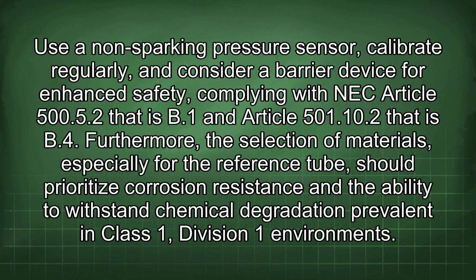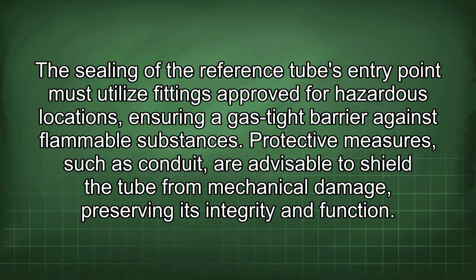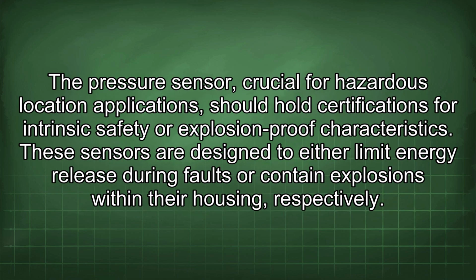Furthermore, the selection of materials, especially for the reference tube, should prioritize corrosion resistance and the ability to withstand chemical degradation prevalent in Class 1, Division 1 environment. The sealing of the reference tube's entry point must utilize fittings approved for hazardous locations, ensuring a gas-tight barrier against flammable substances. Protective measures, such as conduit, are advisable to shield the tube from mechanical damage, preserving its integrity and function. The pressure sensor, crucial for hazardous location applications, should hold certifications for intrinsic safety or explosion-proof characteristics. These sensors are designed to either limit energy release during faults or contain explosions within their housing, respectively.